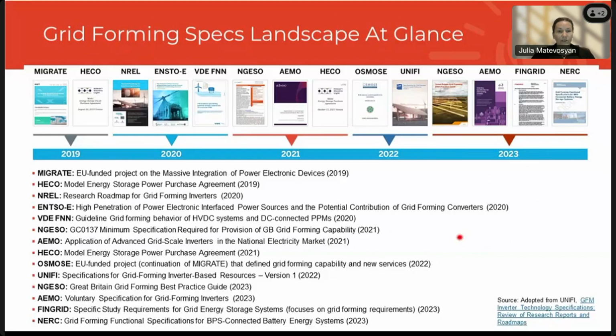All right, so just to go through a landscape of what is happening with grid forming specification requirements. So it all started at the high level, where people just looked at what functionality may be required from inverter-based resources going forward as we reach percentages higher than 75-80% of inverter-based resources on a given system. So there was an EU-funded project called Migrate that proposed these first functionalities that may be needed from inverter-based resources.